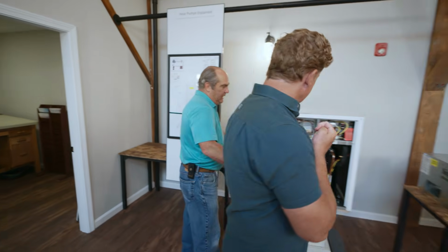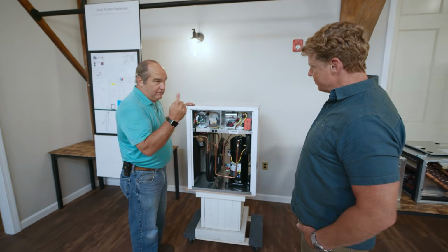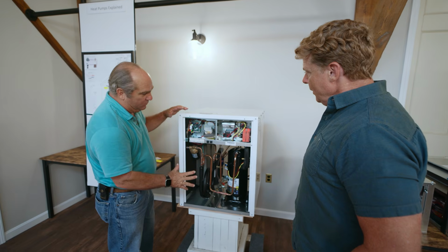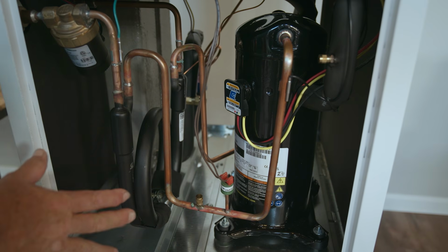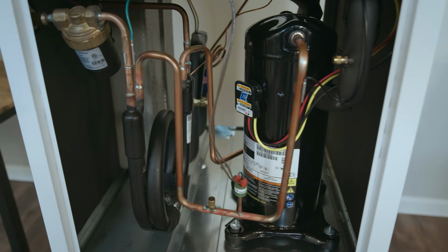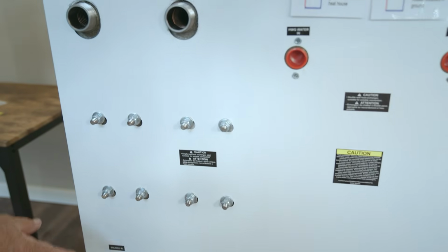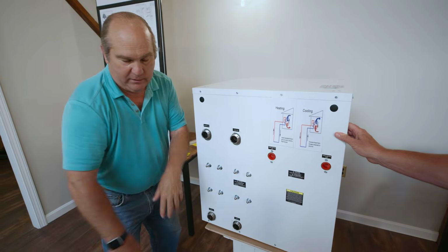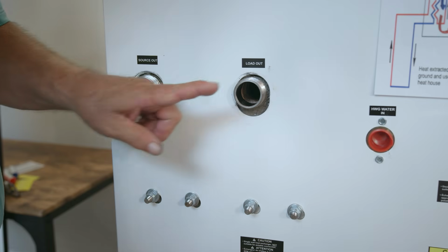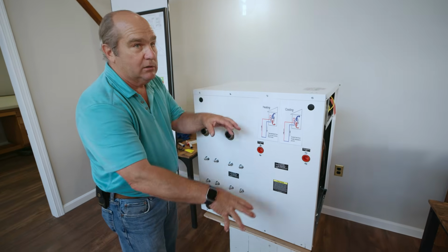Here's our lineup. Here's our geothermal heat pump. This is one of 2 that we'll have in the building. For simplicity, I just have the one. Compressor, expansion valve, reversing valve inside here. You can see there's tappings right here. This goes out to our wells down, and it could go 400 or 500 feet. This goes to our piping inside the building, to our load.